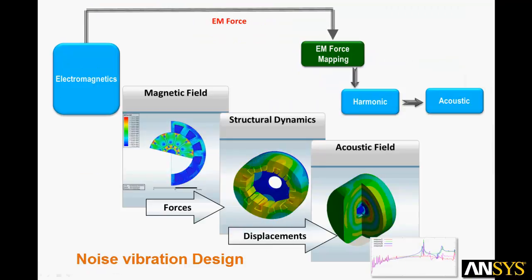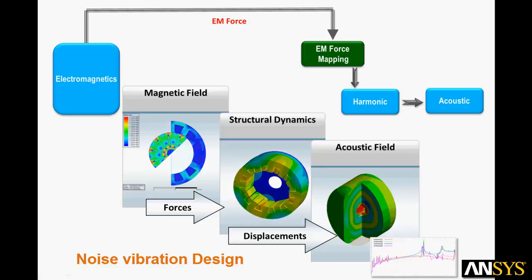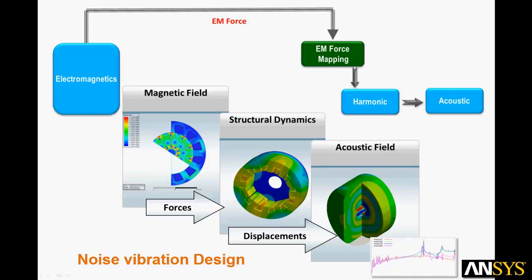For the final analysis, we passed transient electromagnetically induced forces to structural dynamics simulation in mechanical to compute structural harmonics. Those harmonics change the shape of the stator, which in turn produces an acoustic field as computed by ANSYS mechanical. As you can see, this approach can be used to predict acoustic noise and hence enables you to apply strategies to reduce that noise.